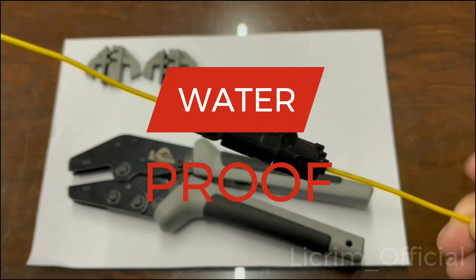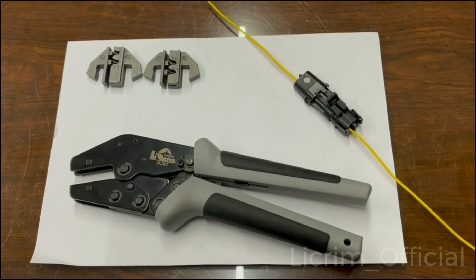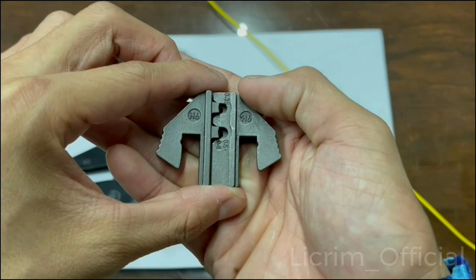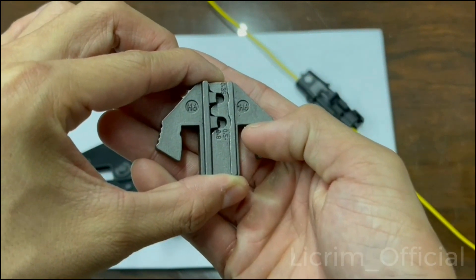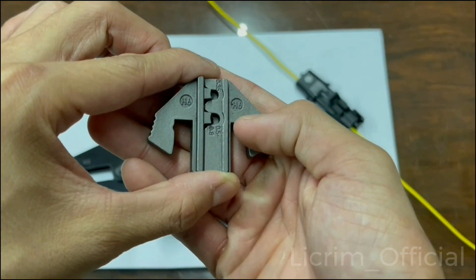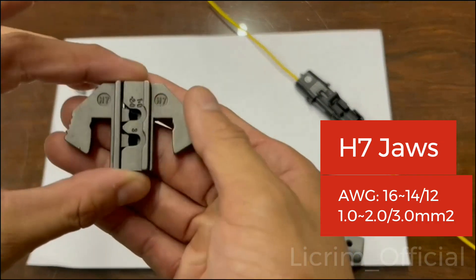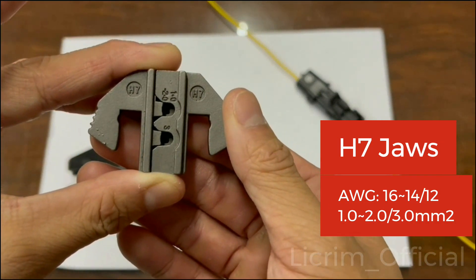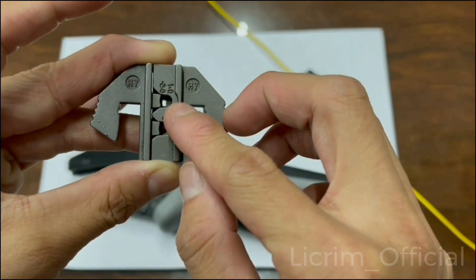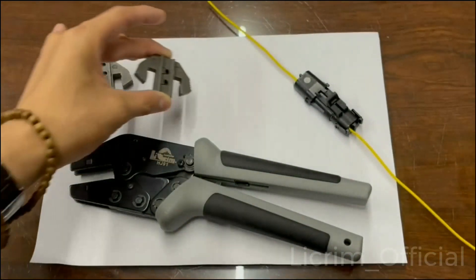Now let's move on to the Jaws. The H6 Jaws is for American wire gauge 22 and 20 to 18, which is 0.35 and 0.5 to 0.8 mm². On the other hand, the H7 Jaws is for AWG 16, 14, and 12, which is 1 to 2 mm² and 3 mm² respectively.